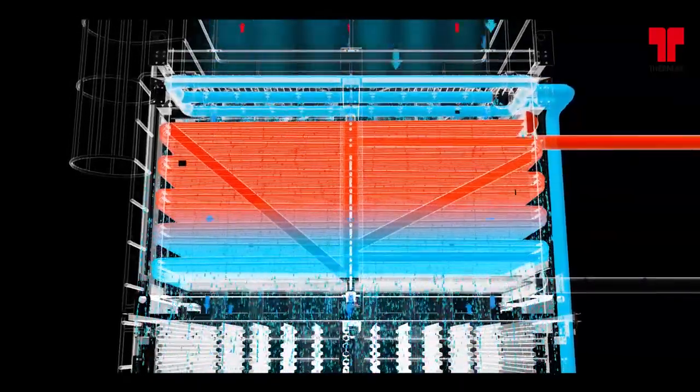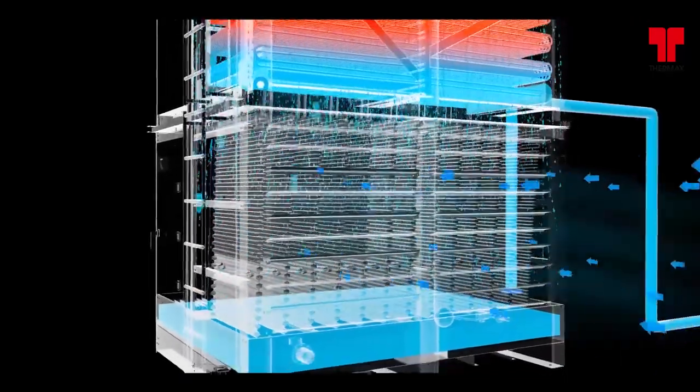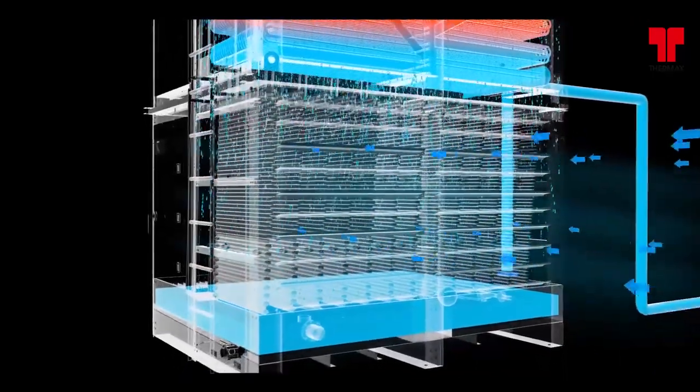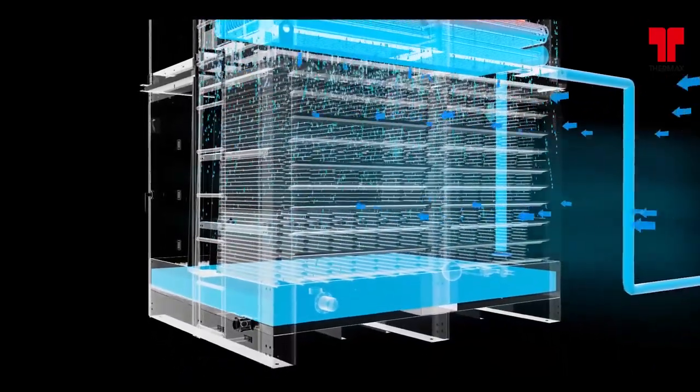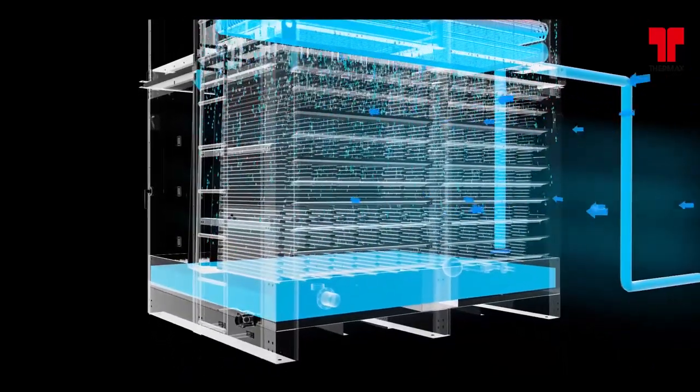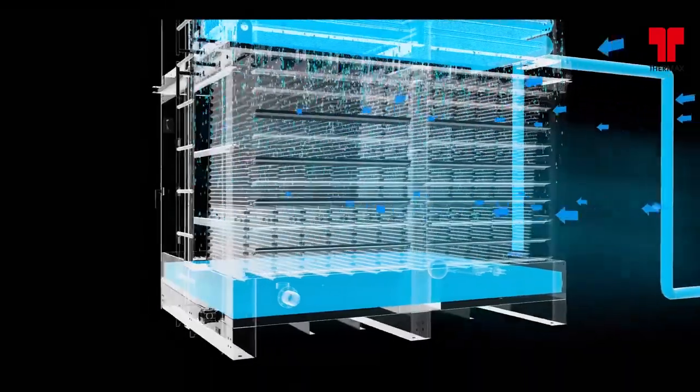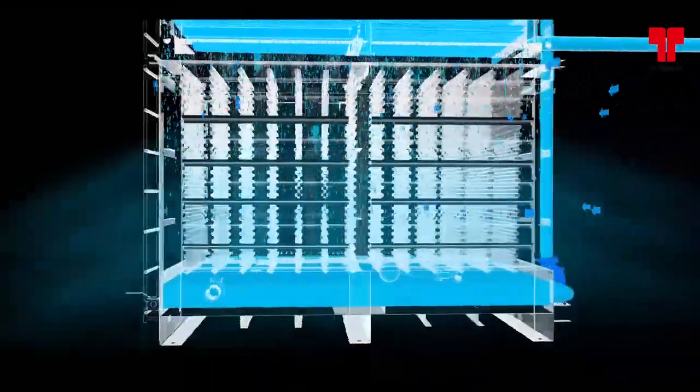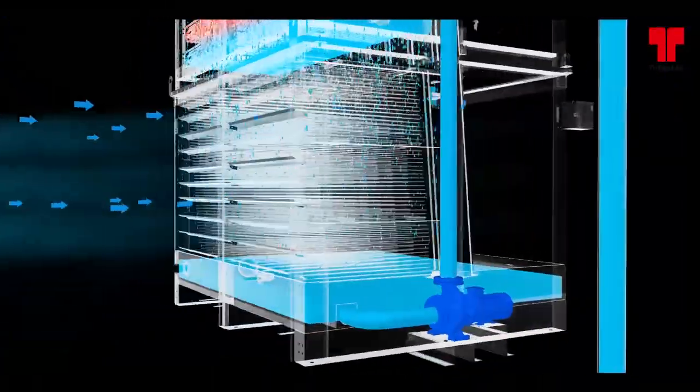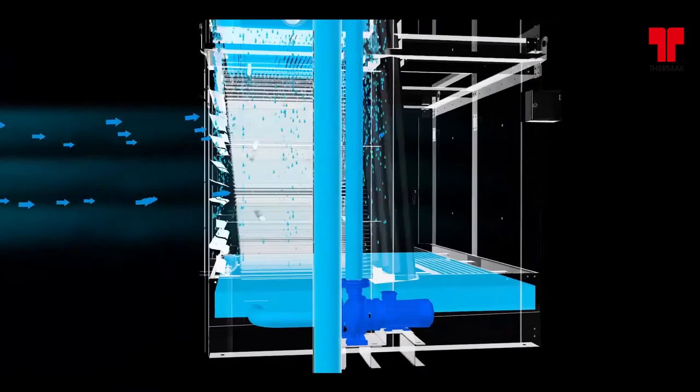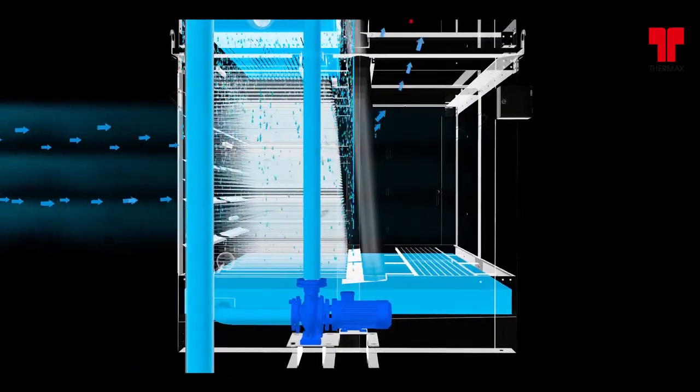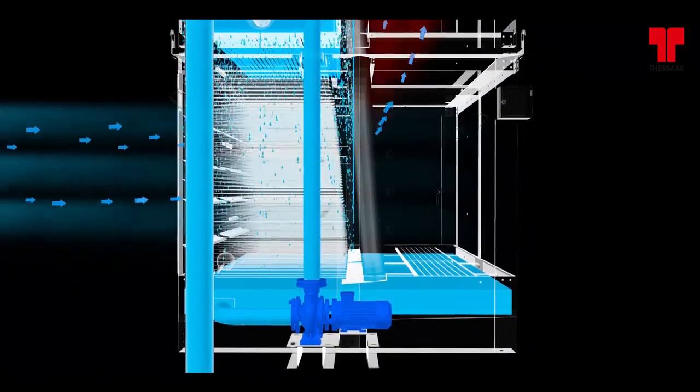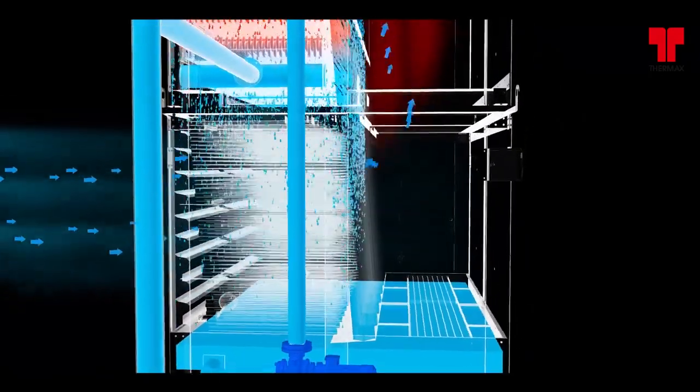Simultaneously, air is also drawn in through the air inlet louvers at the base of the condenser and travels through the heat exchange fills at a direction perpendicular to the direction of the spray water flow, where the water is evaporated, removing the heat and cooling the spray water.